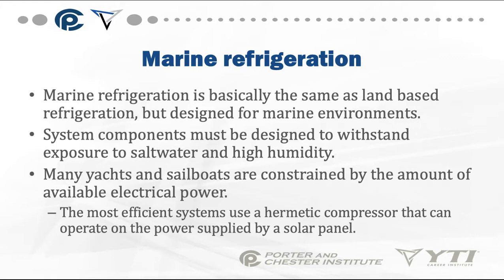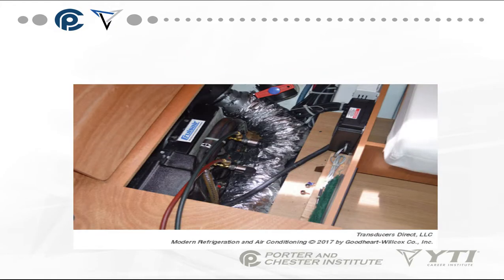Marine refrigeration is basically the same as land-based refrigeration but designed for marine environments. System components must be designed to withstand exposure to salt water and high humidity. Many yachts and sailboats are constrained by the amount of available electric power, so the most efficient systems use a hermetic compressor that can operate on power supplied by a solar panel. This example of a small marine refrigeration system is located under a deck plate — it has to be small in size, lightweight, and able to be cooled.